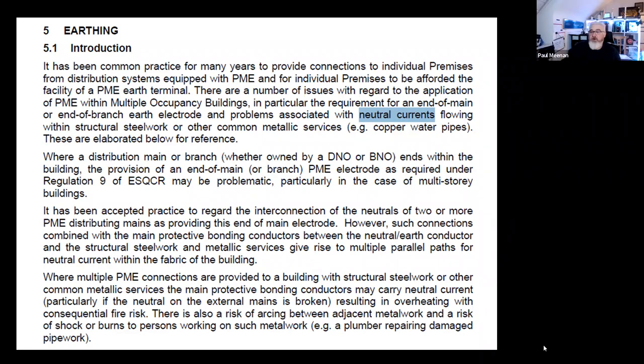Plumbers, especially if you've got a broken PEN or a high impedance PEN, and you've got a water main, potentially that could mask this. And it only will you then find out when you take the boiler off and you potentially get 240 volts. Mm-hmm.